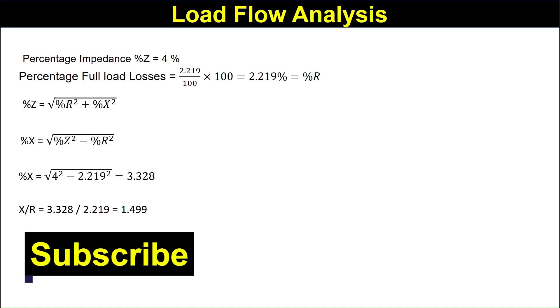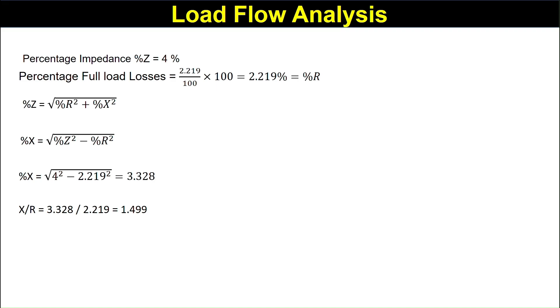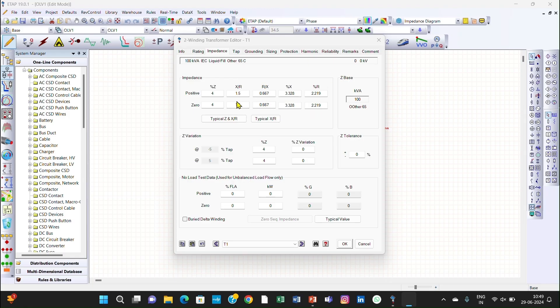Now, we will compare these results with the ETAP result. See, this is the ETAP. The result has the percentage impedance is 4, X by R is 1.5 and we have calculated 1.4999, that is 1.5 and percentage R is 2.219.